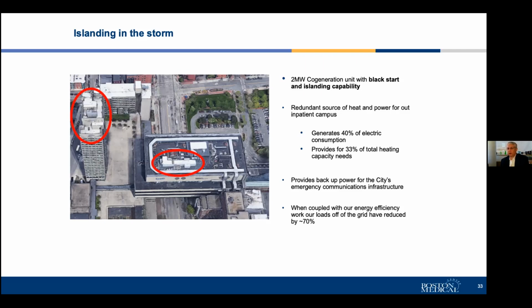Now the two megawatt unit is sized, as Bill mentioned earlier, so that it will use 100%, almost 100% of the time, so that it would maximize the efficiency of the unit. We wouldn't have waste heat that wasn't being utilized. In doing that, it doesn't generate all of the electricity or all of the heat needs we would need for the campus, but it does generate enough that we know we can keep our important inpatient buildings and patient care areas that we know we would need in a disaster fully operational.